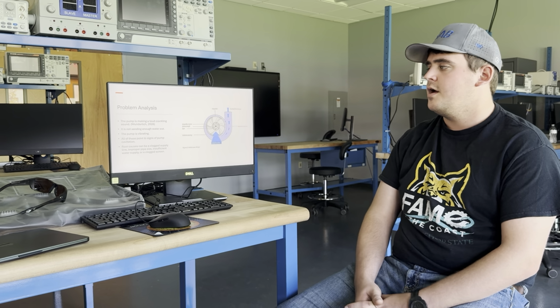Problem analysis. Somebody walked past this pump one day and realized it was making a very large crackling sound. And they also noticed that the equipment was not getting the proper amount of water. These signs can point to pump cavitation. Root causes can be a clogged supply line, improper piping size, or insufficient water supply due to a clogged filter screen.